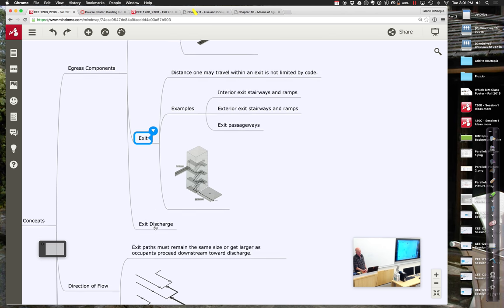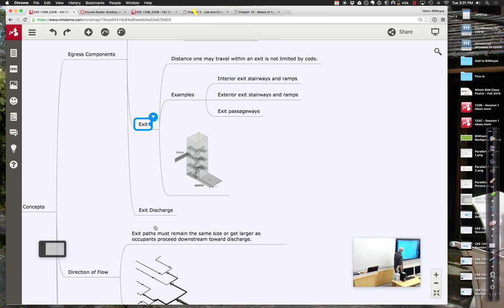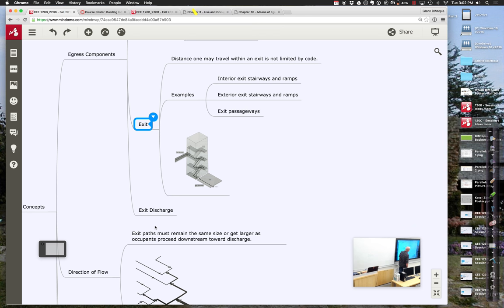The exit itself has no distance limit by code. Once you're in that stairway, it doesn't matter whether you travel two stories or a hundred stories — if the stairway is designed in a fire-safe way, you're in the safe zone. We can have interior stairways, exterior stairways, or exit passageways. Often around the stairway there'll be extra construction — concrete or multiple layers of sheet rock — creating a two-hour fire barrier. Once you're in that zone, you're considered fairly safe.